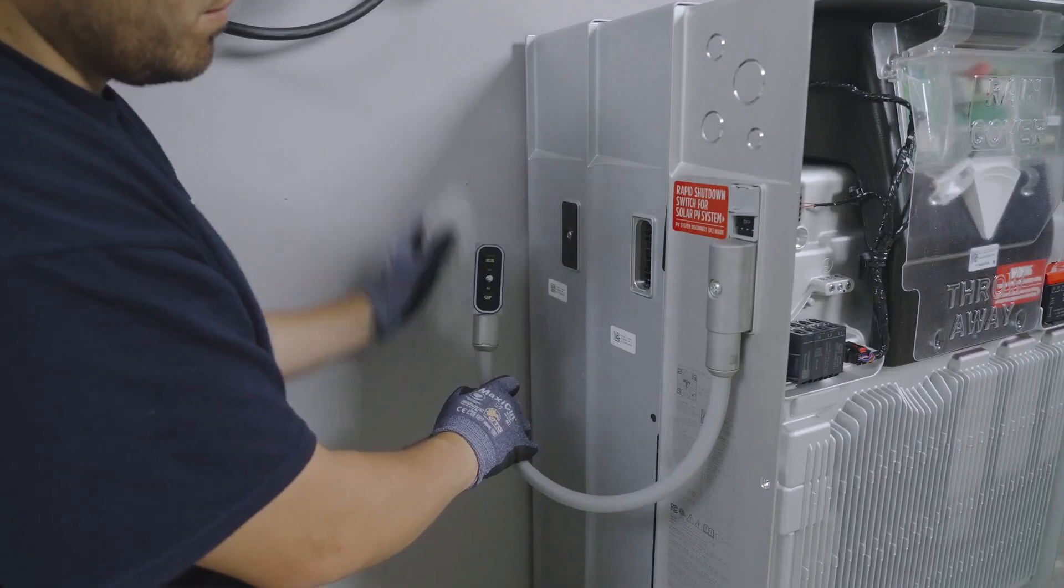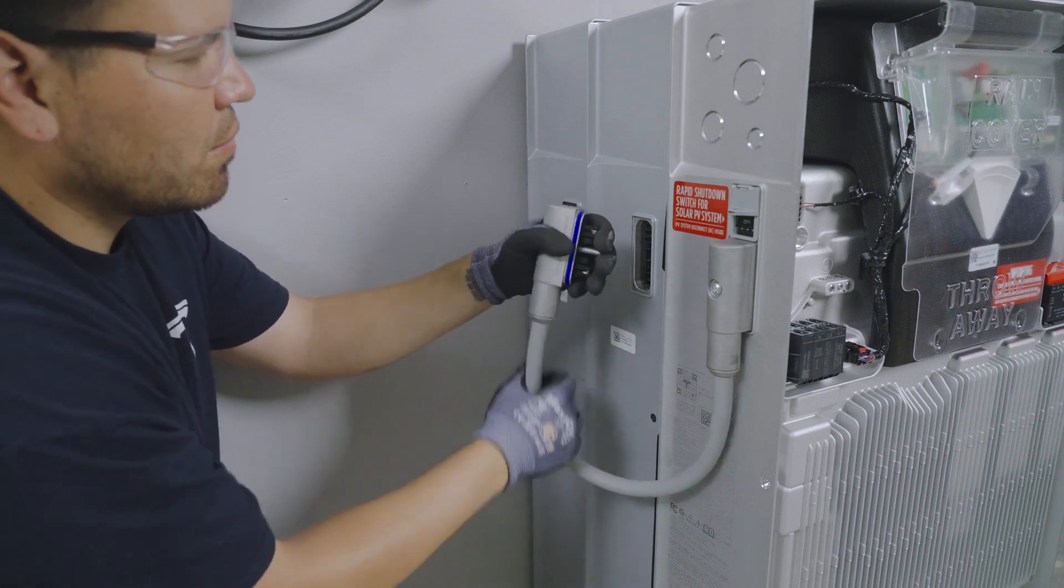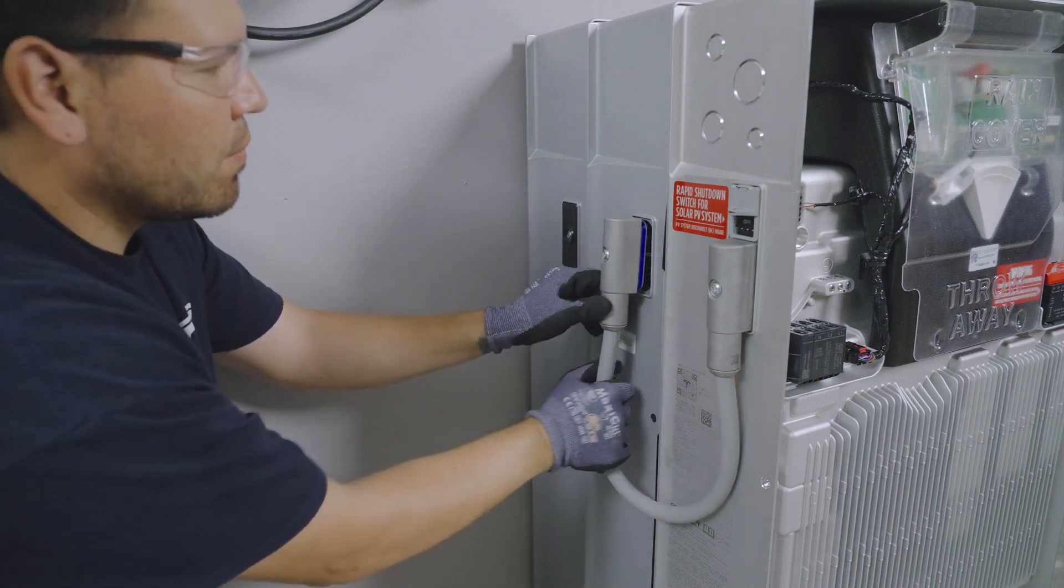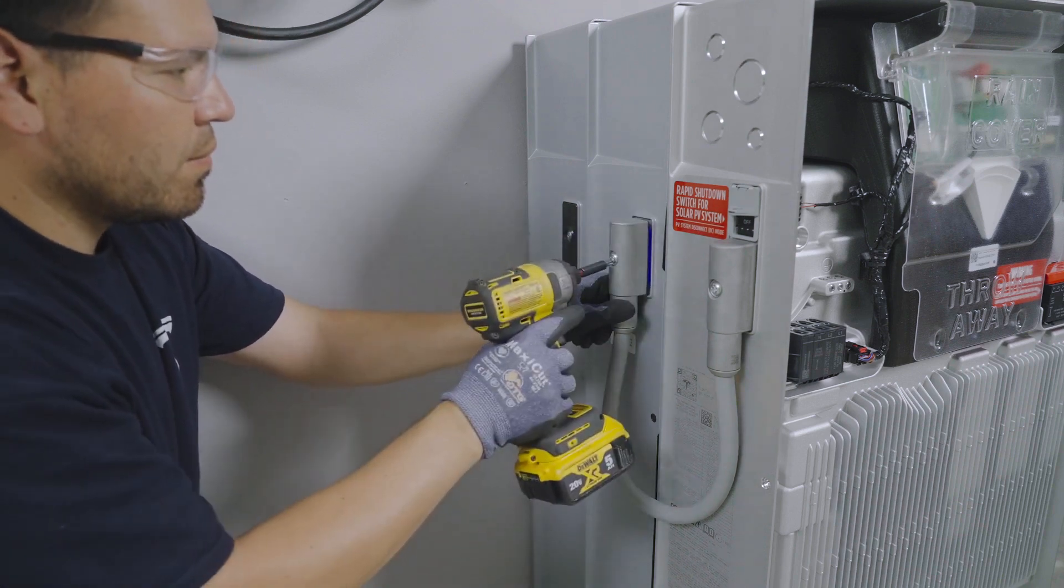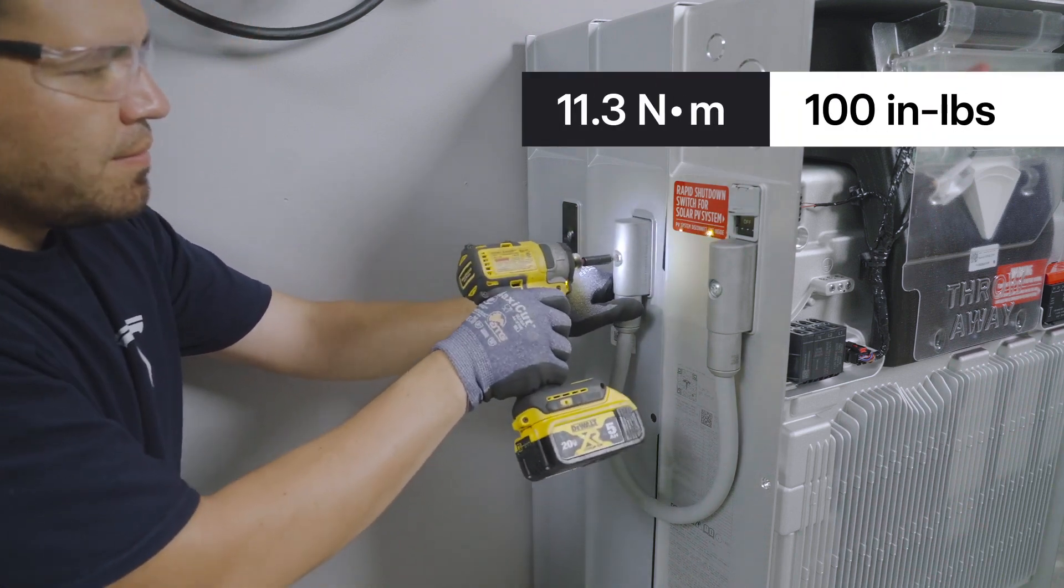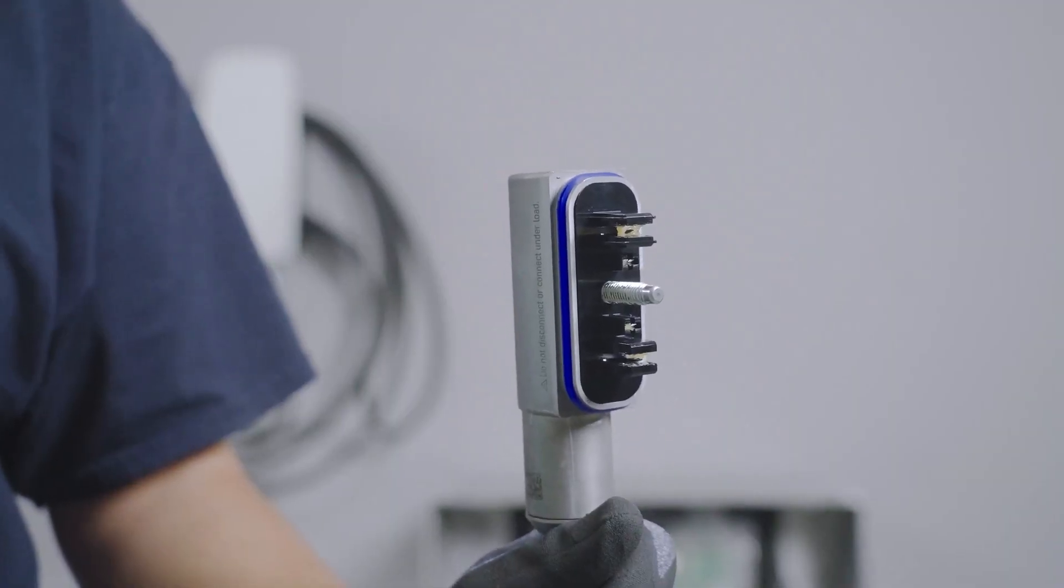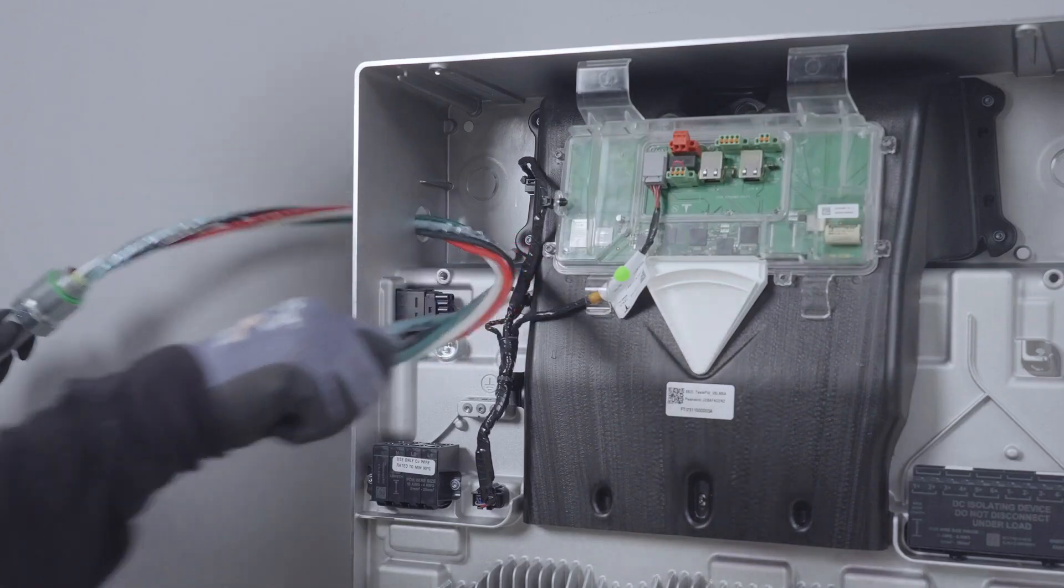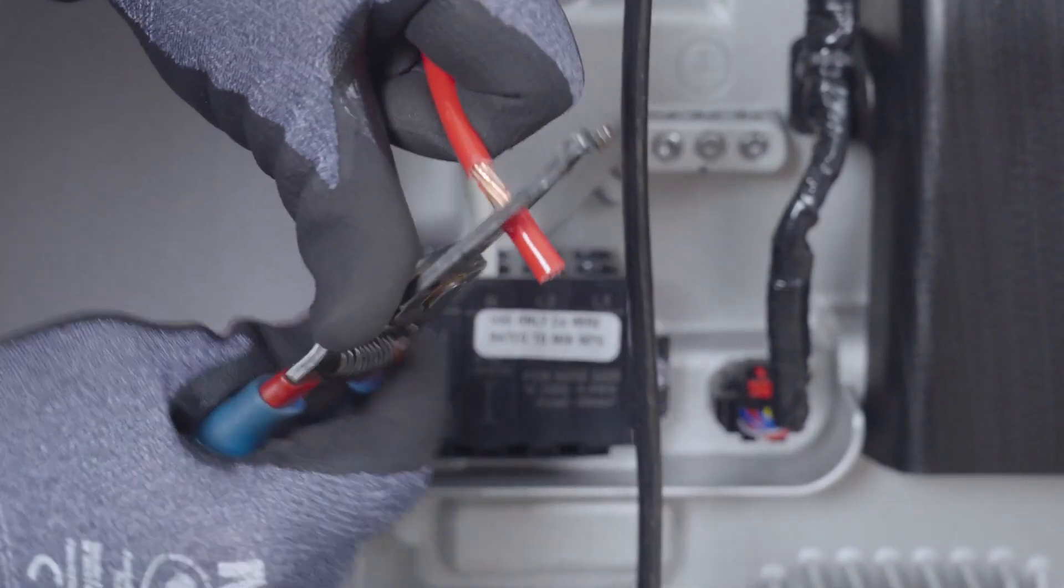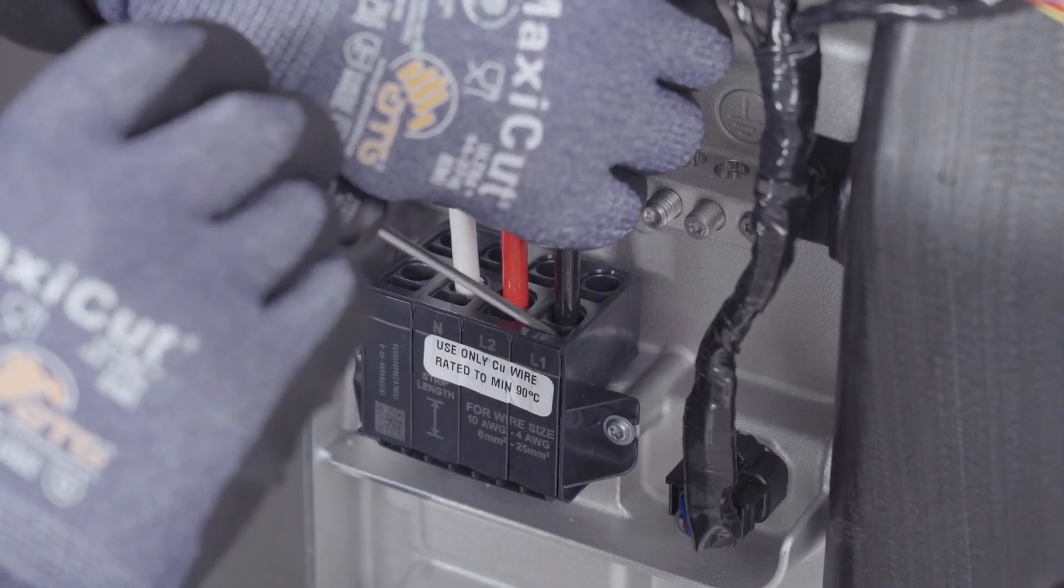Route the other end of the wiring harness to the next unit, either another expansion or Powerwall 3. Connect the other end of the wiring harness to the next unit and secure with a T40 screw, tightening to the specified torque value. If a wiring harness is dropped or otherwise damaged, dispose of it and use a new harness. Follow the standard procedure to connect branch circuit wiring to Powerwall 3, located at the front of the stack.